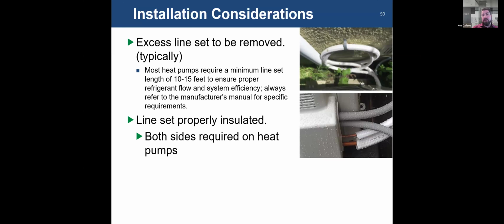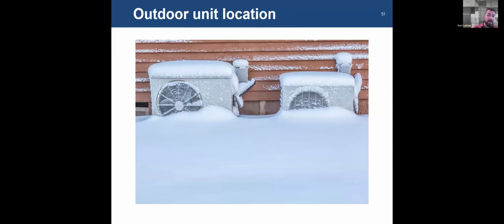On heat pumps, both sides need to be insulated. It's not always a liquid and a vapor line. Both switch roles, right? So cold and hot, depending on the mode of operation. And again, for cold weather climate heat pump installations, make sure you are above the snow line, right? The snow design parameters in that area, and make sure you have enough space underneath for proper drainage so that you do have good operation and you're not burying your units in snow.